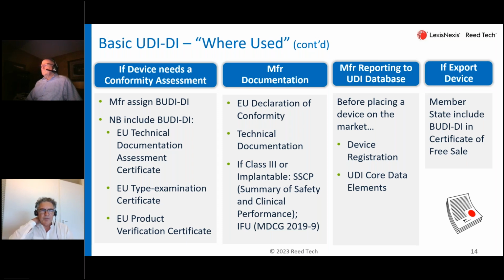And also, if you go to a notified body, they want to know what they will be looking at. So they need to know the Basic UDI for each risk class and subclass of devices. So they must know what they are looking at, so they can set up their sampling strategy.